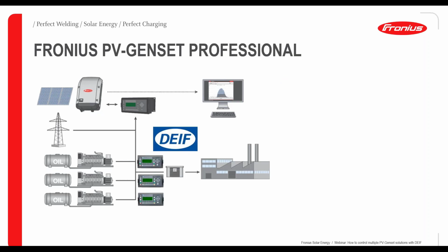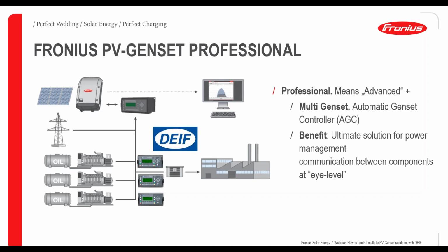And a step forward is the professional solution. The difference which we can see here is that we have all the benefits that we have with the advanced, but now every diesel generator within the system has its own automatic genset controller. Therefore we have communication between the components for regulating the system on eye level. So all the DEIF components are communicating on eye level, and therefore it's the ultimate solution for power management. If we're talking about a new solution, not a retrofit, this would be the perfect solution.